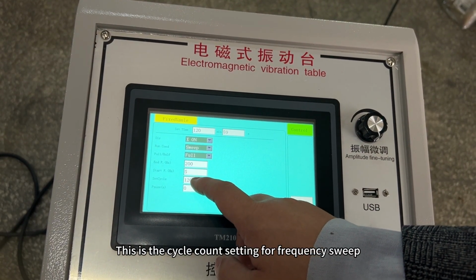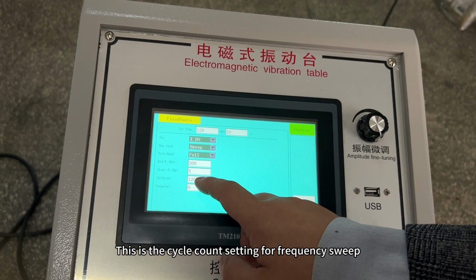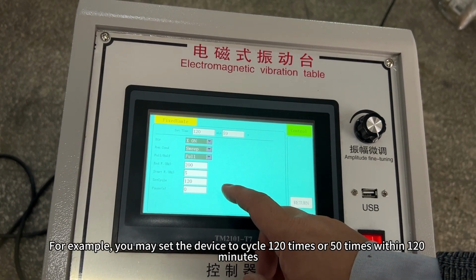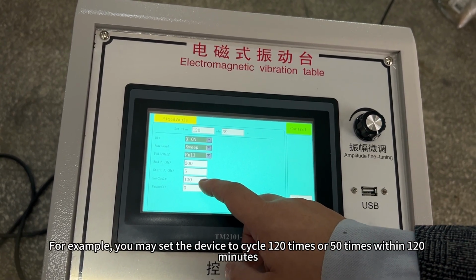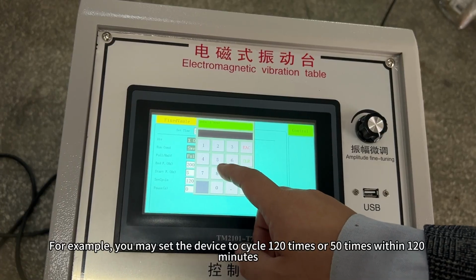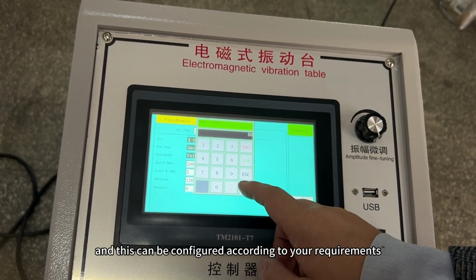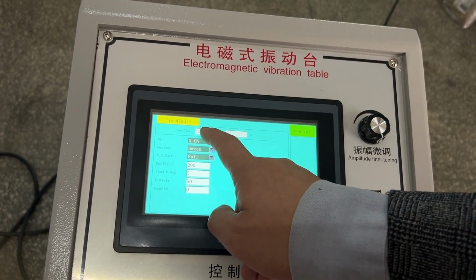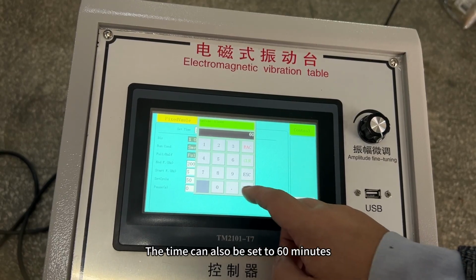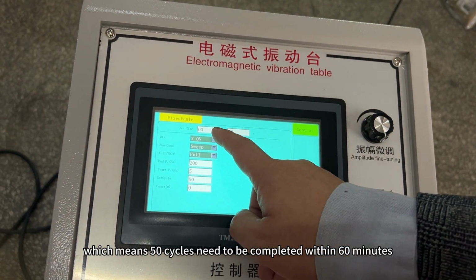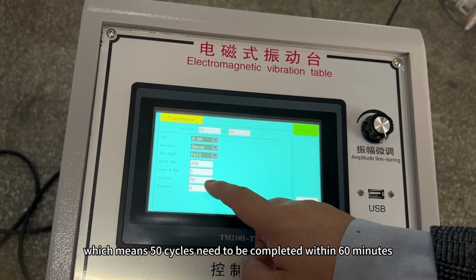This is the cycle count setting for frequency sweep. For example, you may set the device to cycle 120 times or 50 times within 120 minutes. And this can be configured according to your requirements. The time can also be set to 60 minutes, which means 50 cycles need to be completed within 60 minutes.